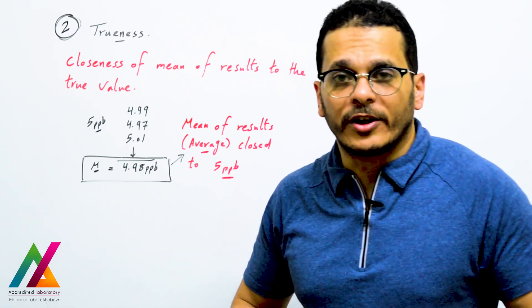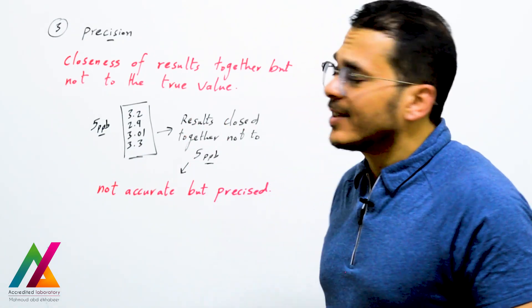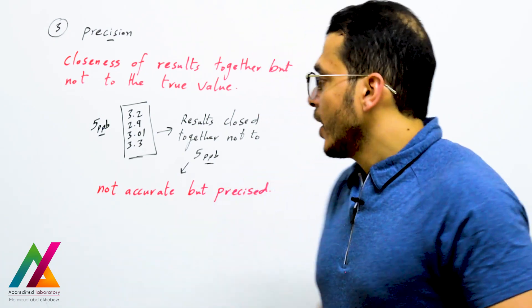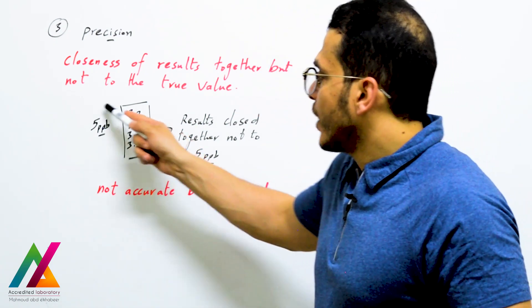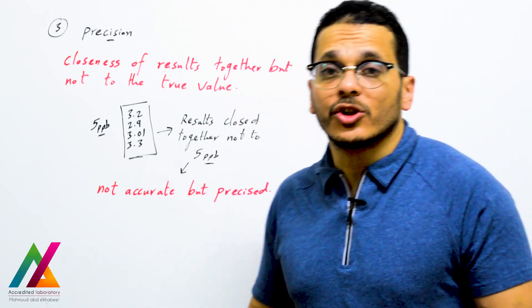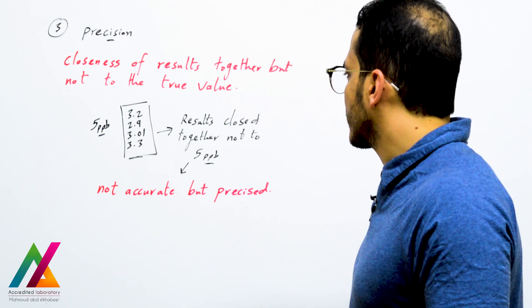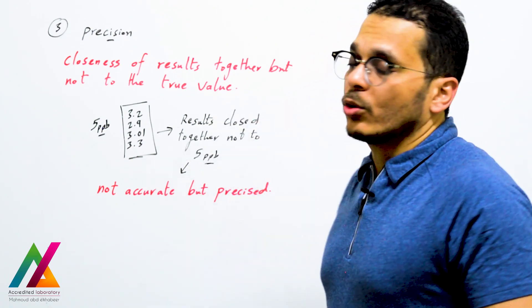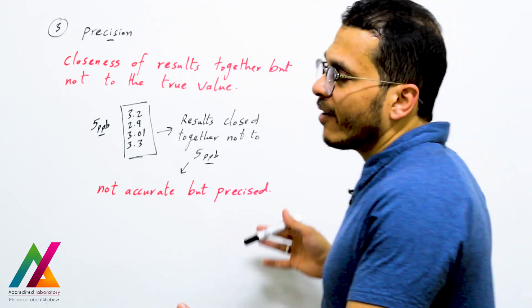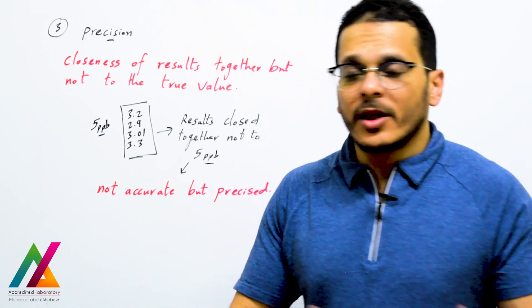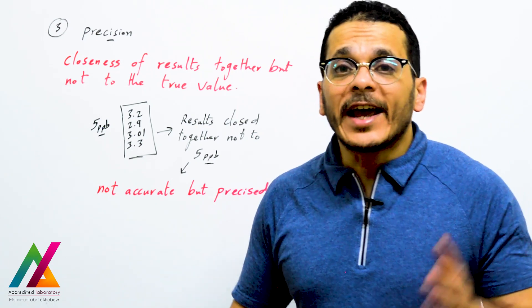Precision, as in the Eurachem guideline, is the closeness of results together but not necessarily to the true value. For example, if you spike with 5 ppb and get 3.2, 2.9, 3.01 — all results are close to each other but not to 5 ppb, the true value. So results can be precise but not accurate. It is better to have results that are both accurate and precise.